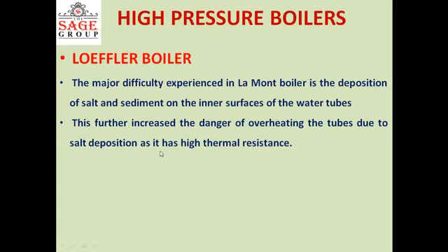If the deposition of salt over the inside surface of the tubes continues to increase, there is the danger of overheating, due to the high thermal resistance of the thick film of salt, and that can cause overheating of the tubes, with further implications also.